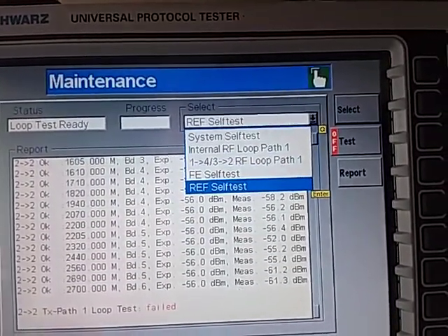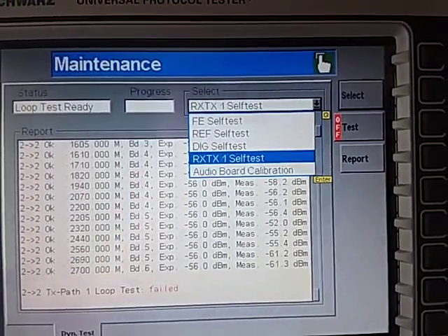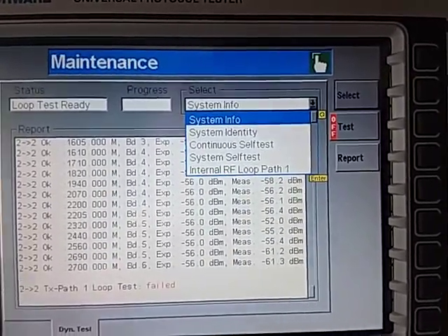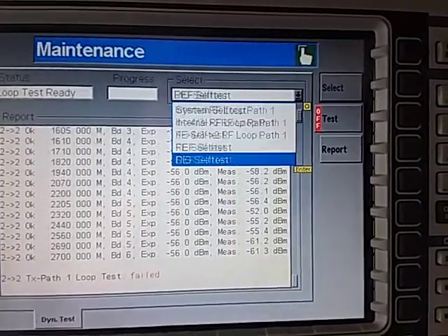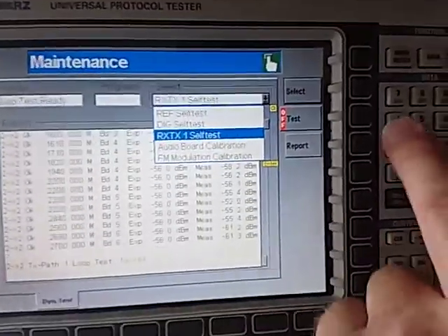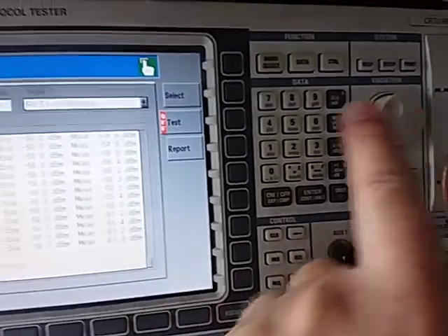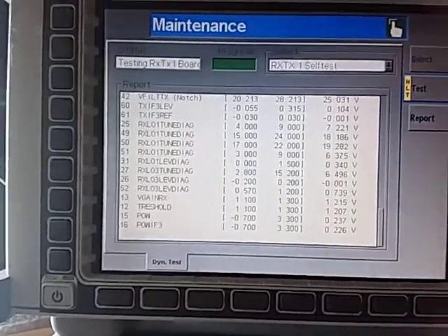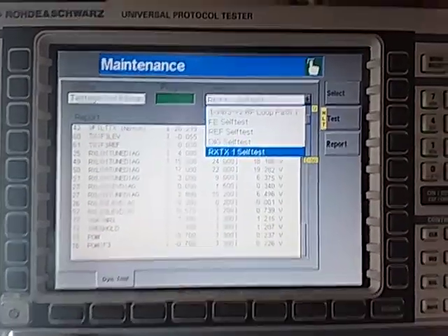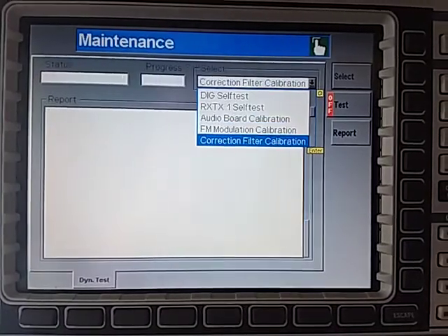These tests here are testing each of the different boards singly. That test before tested all of those together. Now we're testing the individual boards and I believe this does a fraction more than what the combined test does. You can just run them, just select it and go okay and run it. It's doing the test and you can see the different things that it's looking for on that board. It's looking for different voltage levels and it's reporting it back to you. It will tell you if it's passed or failed. It's a great way of finding out if any of your boards are faulty in the analyzer.